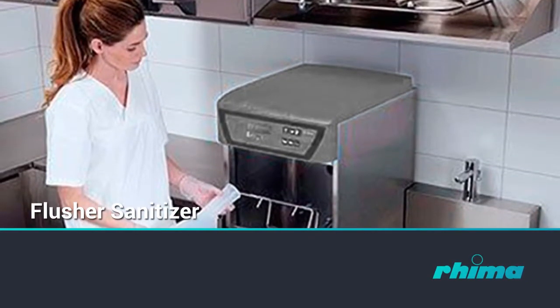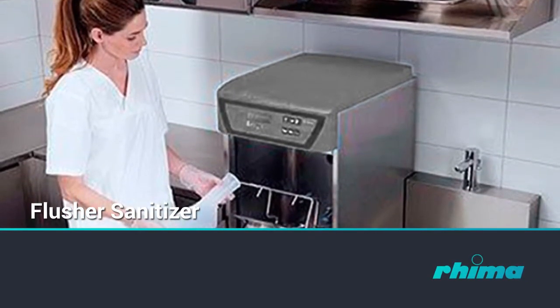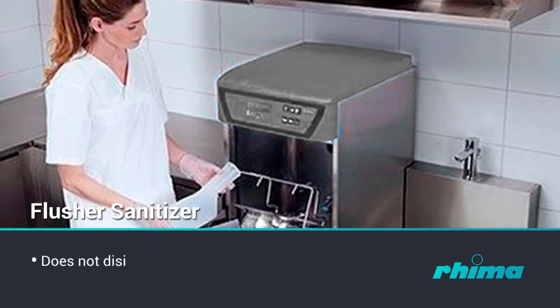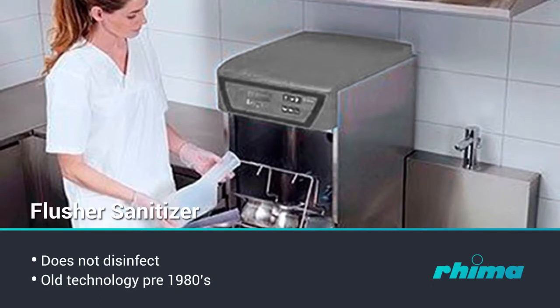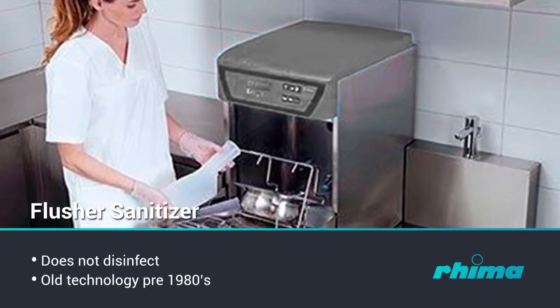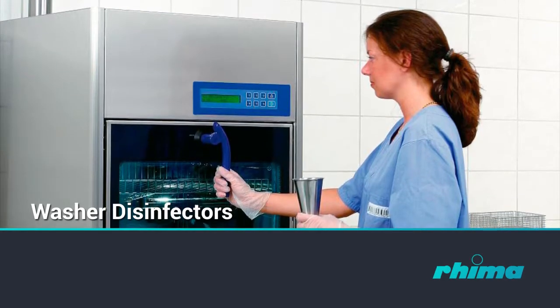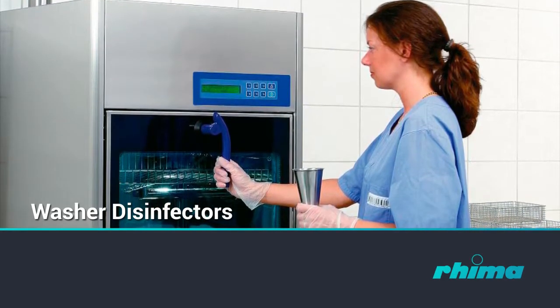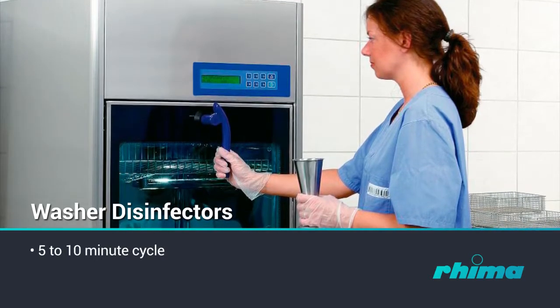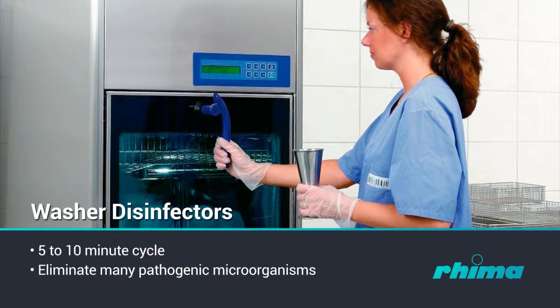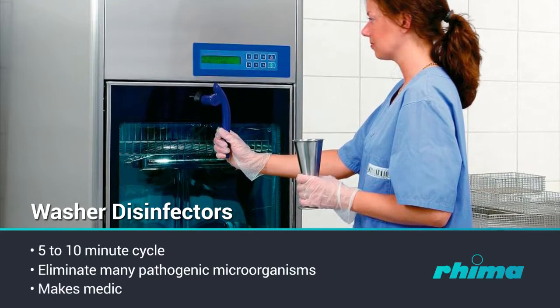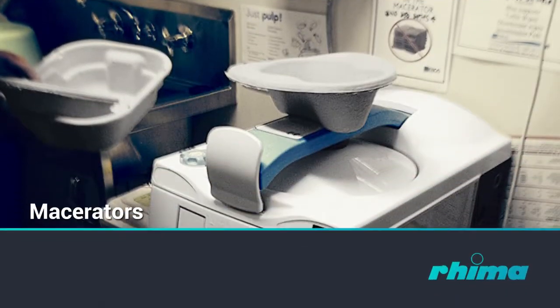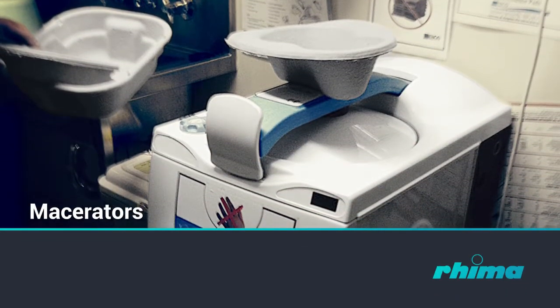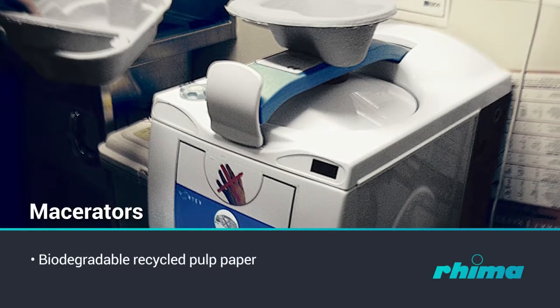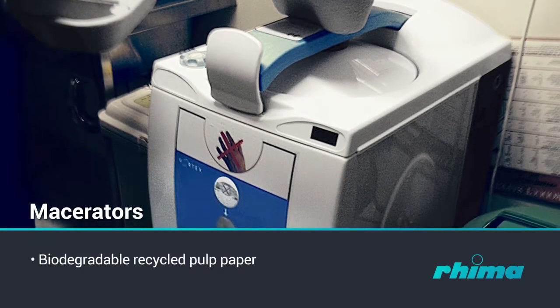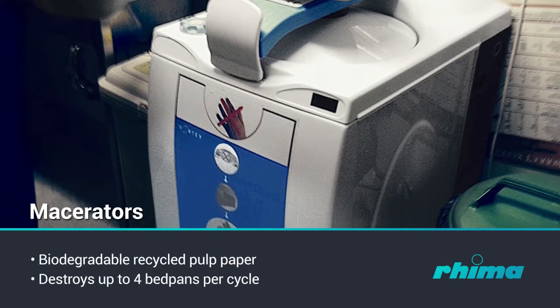Flusher sanitizer, a basic unit that you use to empty and rinse contents of bedpans and urine bottles. It does not disinfect them. Old technology that is being phased out of most hospitals and care facilities. Washer disinfectors, a machine that empties, rinses and has a disinfection cycle. Disinfection is an important process intended to eliminate as many pathogenic microorganisms as possible from medical devices to make them safe to reuse. Macerators grind up disposable bedpans made of biodegradable recycled pulp paper. When in use, disposable bedpans are placed on reusable plastic supports that must be cleaned and disinfected.